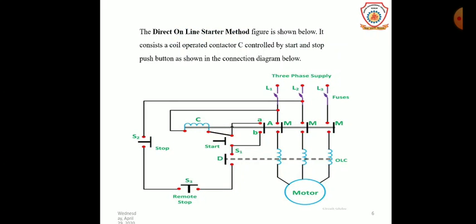The direct online starter circuit consists of a coil-operated contactor controlled by start and stop push buttons. S1 is normally open and S2 is normally closed. At start, S1 is closed for a fraction of a second, due to which the coil gets energized and attracts the contactor, so the motor directly gets supply. An additional contact ensures that as long as supply is on, the coil gets supply and keeps the contactor in its own position. When S2 is pressed, the coil circuit opens, the coil gets de-energized, and the motor is switched off from the supply.